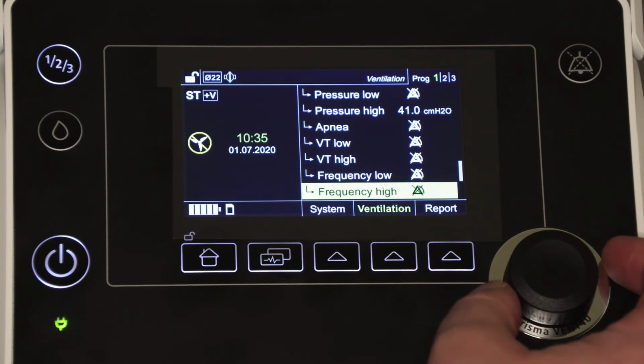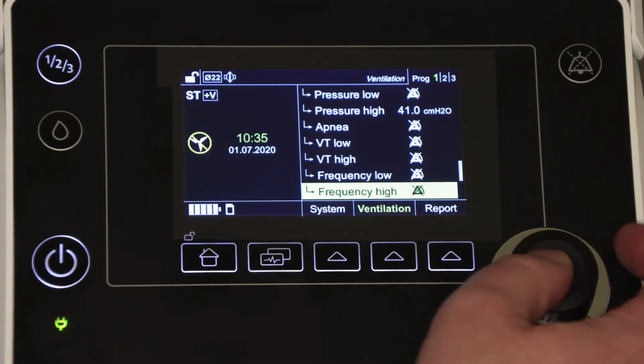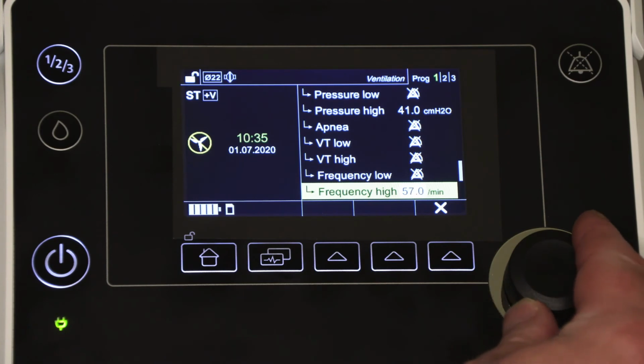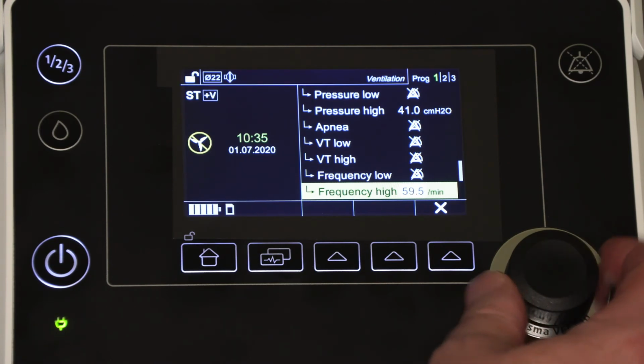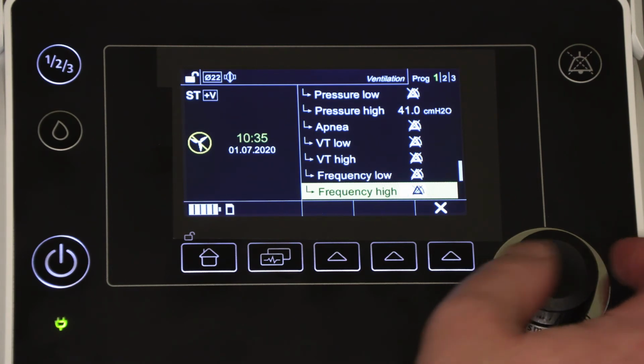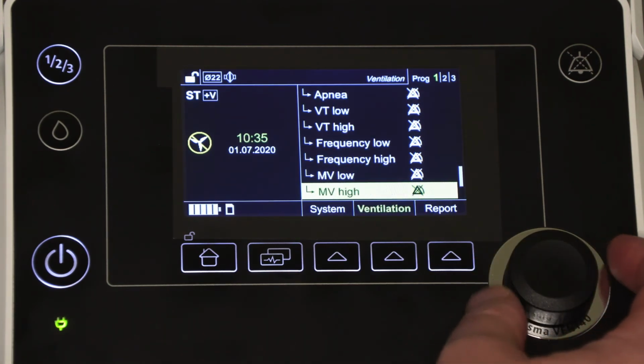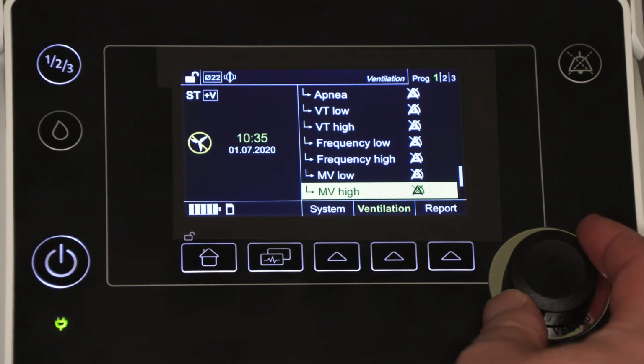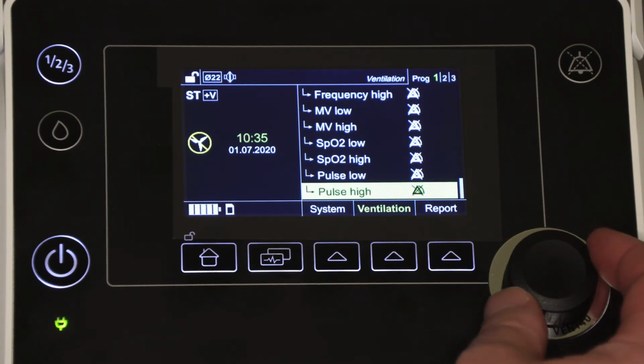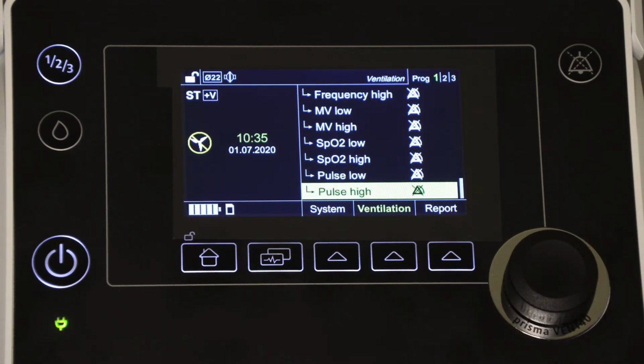low and high frequency, which is low and high breath rate, and can be set to warn if a patient's respiratory rate falls below the low alarm setting or exceeds the high alarm setting. There's also low and high minute ventilation alarms, and then the high and low SpO2 and pulse alarms. All or any of these alarms, if necessary, can be turned on and set to the required values.